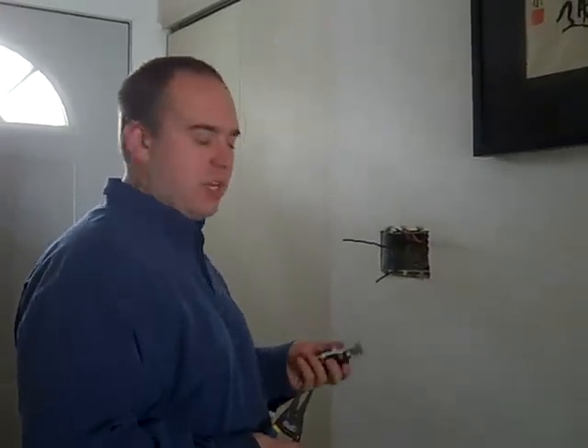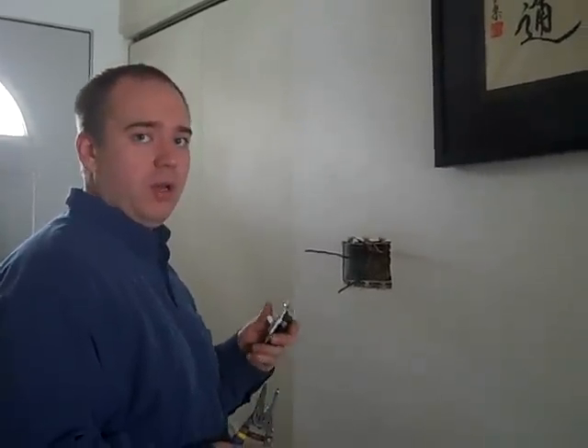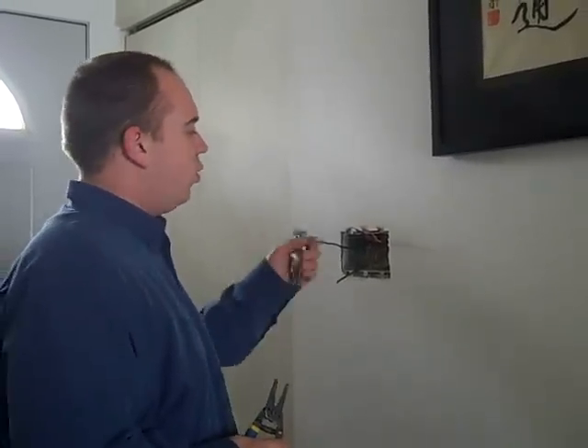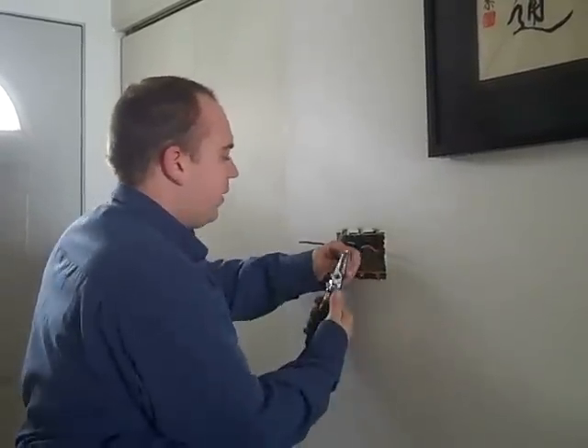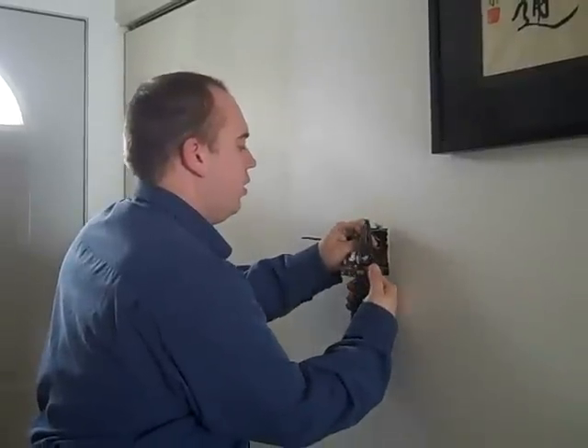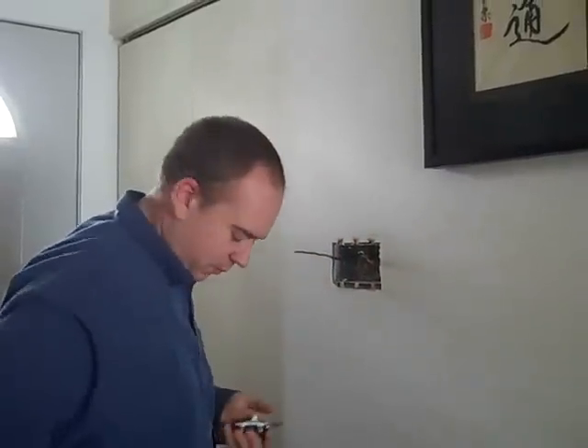In a house of this age, if you just want to update your electrical devices, all we need to do is take off the improper copper-rated devices. We have our CO/ALR switch, which is appropriate for aluminum wire. We've removed all the old devices, take our aluminum wire, strip it back, and put the CO/ALR switch right on the wire just like we would with anything else. This is perfectly acceptable for use with aluminum wire.